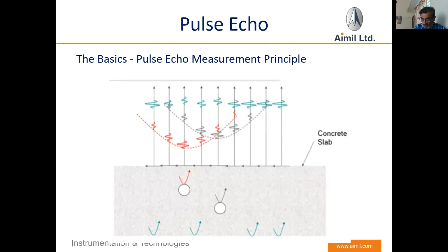This is the multi-channel transducer. In case of UPV, you have a single channel, a receiver and transmitter, one channel. Here it is a multi-channel transducer. So now you can see some of the points. It is 3 into 8: 1, 2, 3, 4, 5, 6, 7, 8. 8 into 3. So in total there are 24 points.